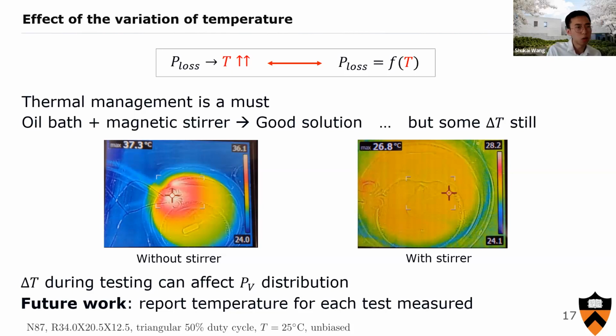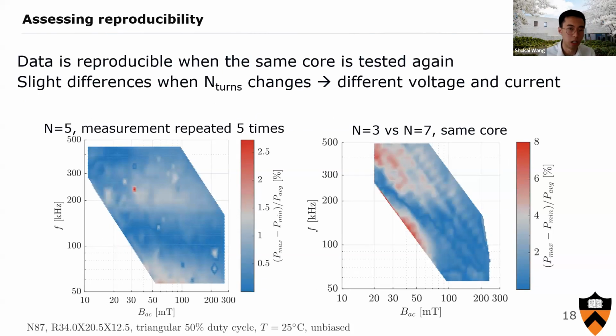Yes, indeed. So after introducing all these sources of error, we have to really assess the reproducibility of our data acquisition system. As you see on the bottom left here, here's an example of us using the exact same core with the same number of turns for our windings, and measuring across a frequency and flux density range at the same temperature and same duty ratio for the same waveform. We repeated that 5 times. As you can see, with this distribution, we see an overall less than 3% error in this subset, for instance. That tells us that our data acquisition system is not varying too much in measuring the same core, so it is actually highly repeatable.